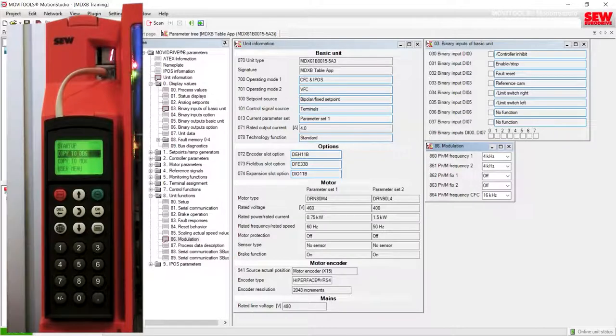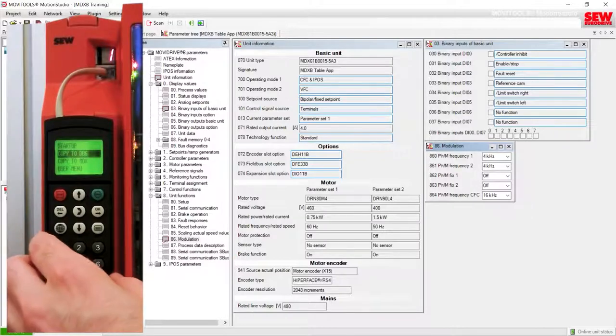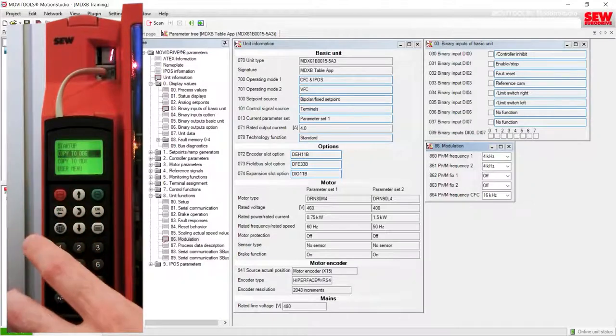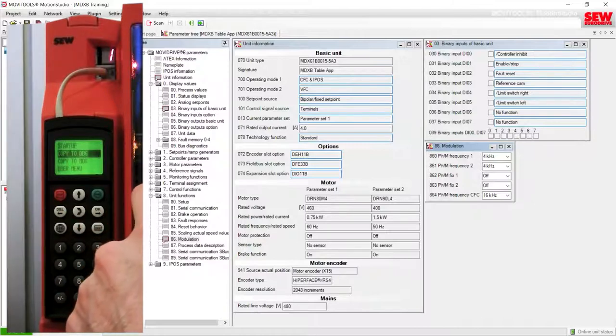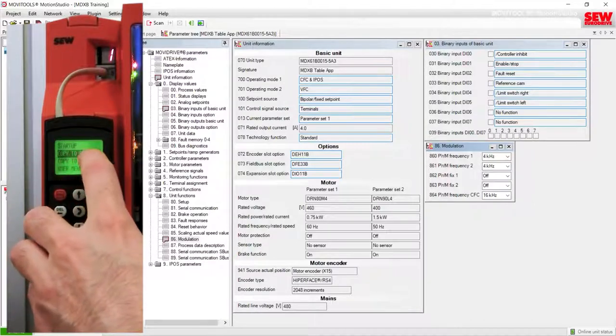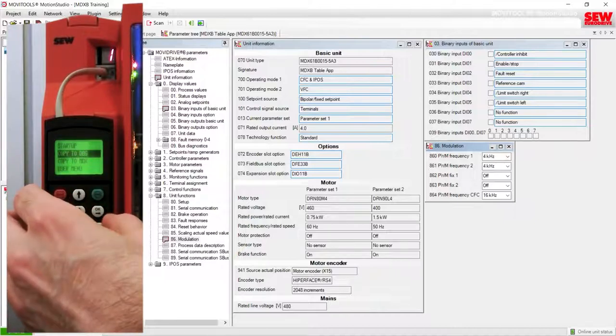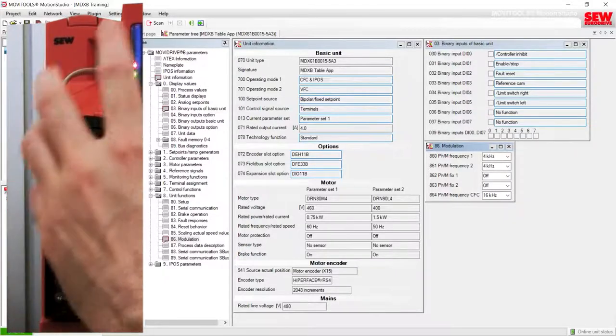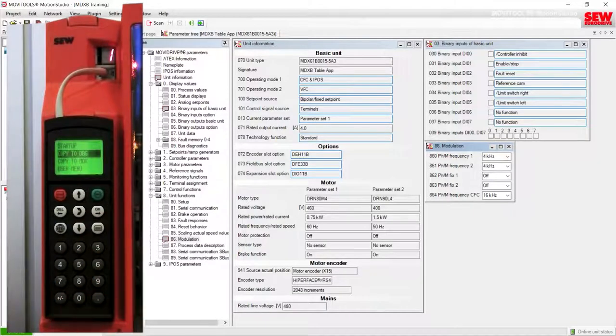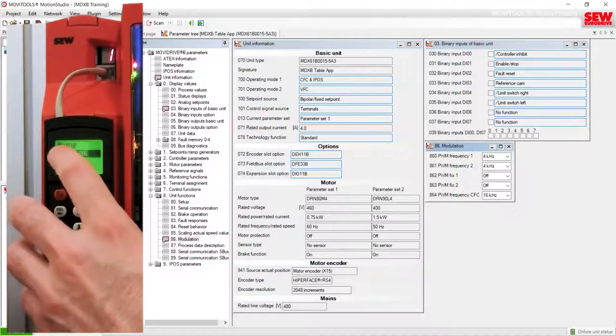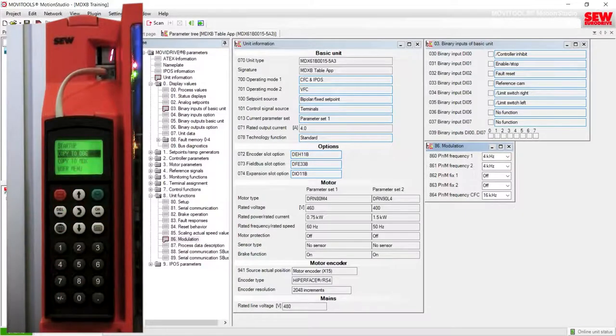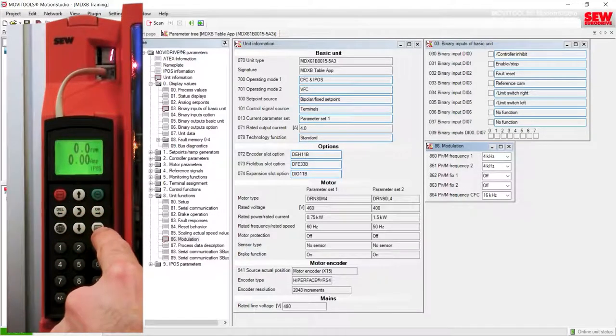The same caution applies in reverse: if you have a good keypad with good parameters and need to replace your MOVIDRIVE, and you accidentally choose copy to DBG first, you would overwrite the good parameters stored on the keypad with whatever is stored in the new MOVIDRIVE, which is likely default parameters. So always be very careful about the file direction you choose when using the keypad to manage the parameter file.